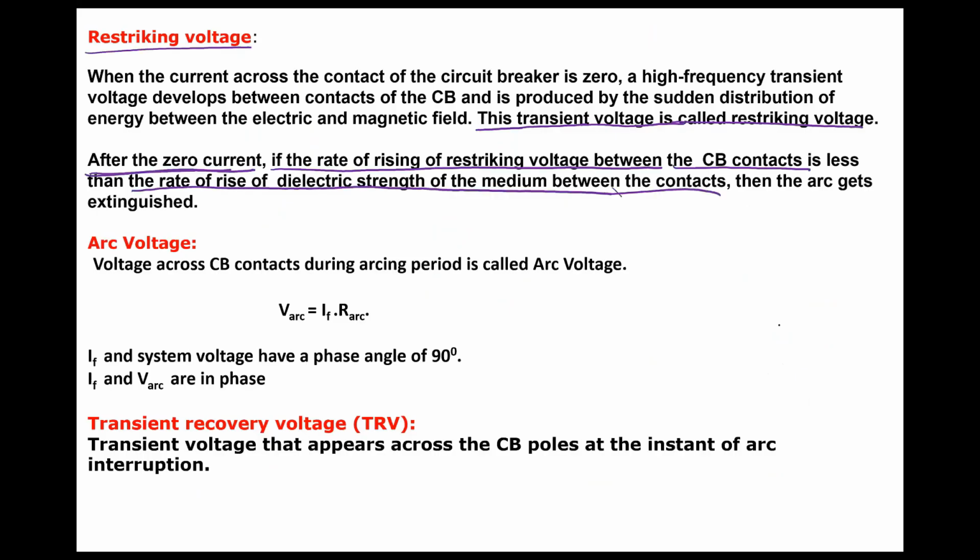So if the dielectric strength rises faster when compared to this transient recovery voltage, then the arc will be completely quenched. The arc will not come back again. However, if the rate of rise of restriking voltage is greater than the rate of rise of dielectric strength of the medium, then the arc will restrike. Understand? So that is the concept of restriking voltage.